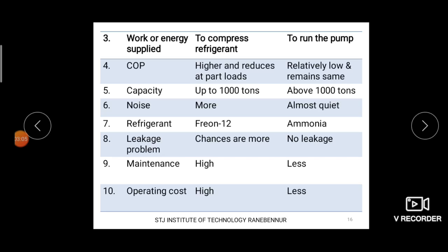The next difference is coefficient of performance. COP will be higher in case of vapor compression system, but it reduces at part loads — that is, under partial load conditions. In vapor absorption refrigerating system, the coefficient of performance is relatively low, but it remains the same under partial load conditions.